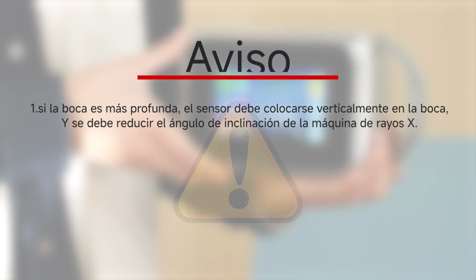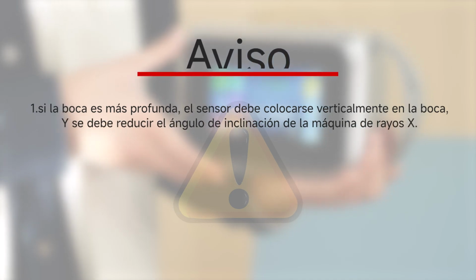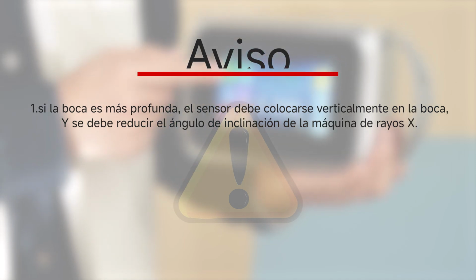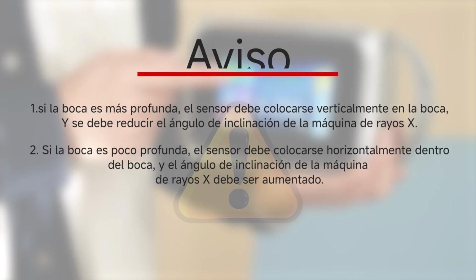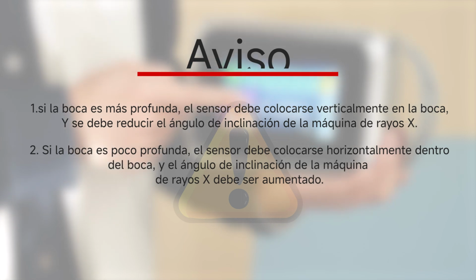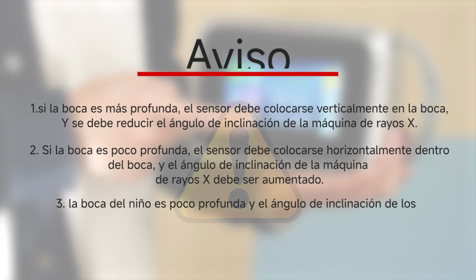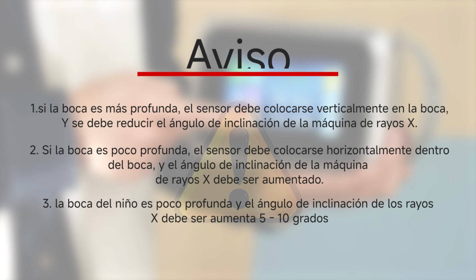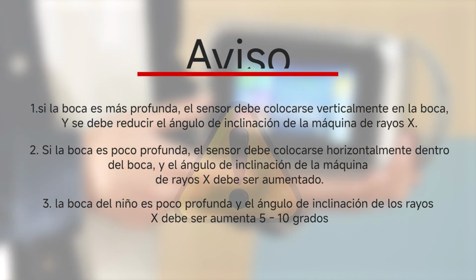If the mouth is deep, the sensor should be placed vertically inside the mouth, and the tilt angle of the X-ray machine should be reduced. If the mouth is shallow, the sensor should be placed horizontally inside the mouth, and the tilt angle of the X-ray machine should be increased. Children's mouth is more shallow, and the tilt angle of X-ray should be increased by 5 to 10 degrees.